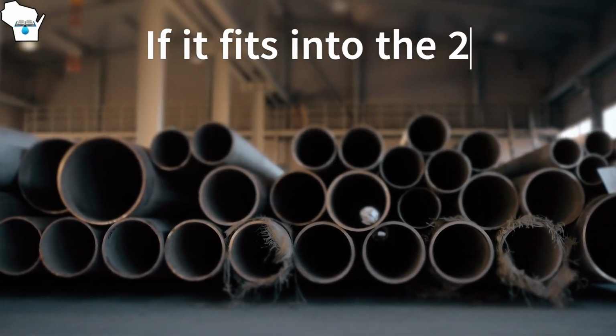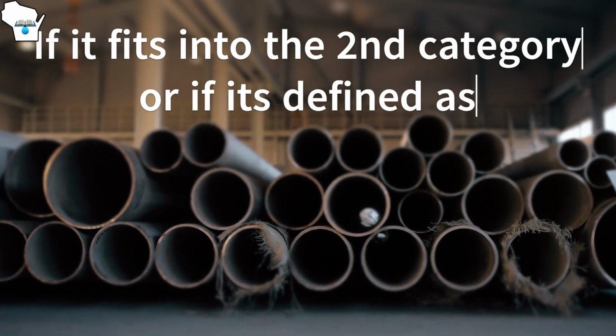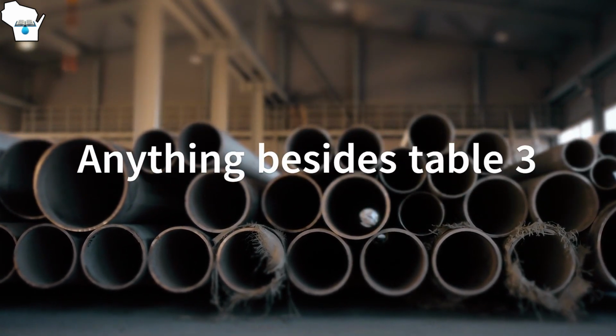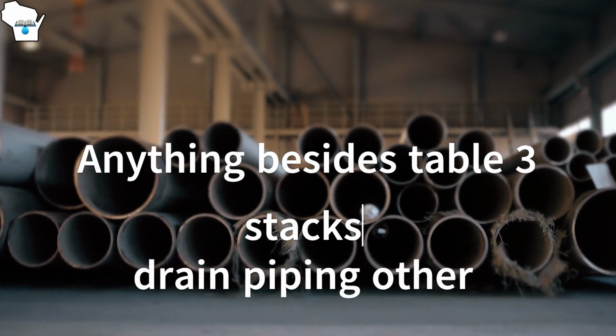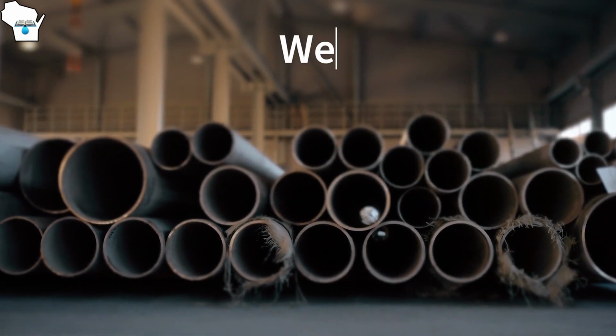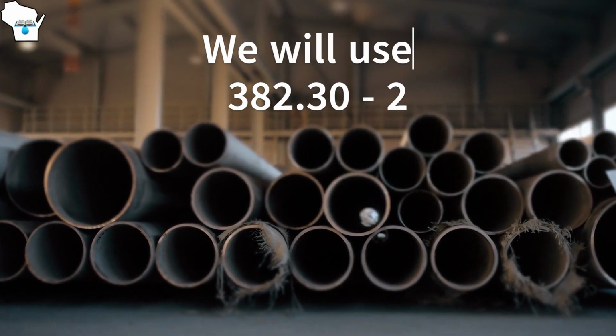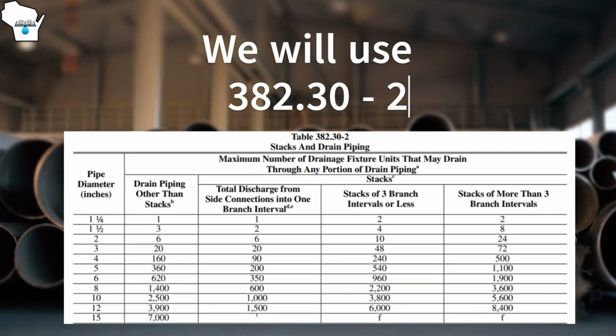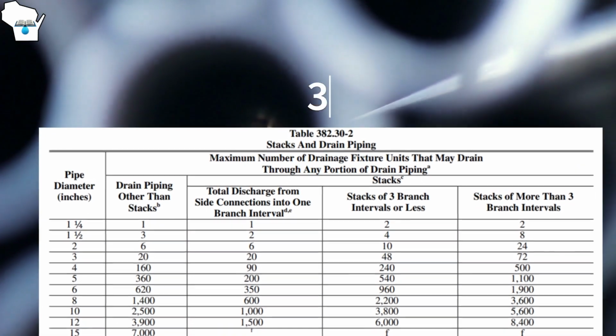Now for the second category, which is essentially all the other piping. So if it doesn't fall into the category of building drain, building subdrain, and building sewer, we would use Table 2 of 382.30, which would incorporate stacks and drain piping other than stacks.